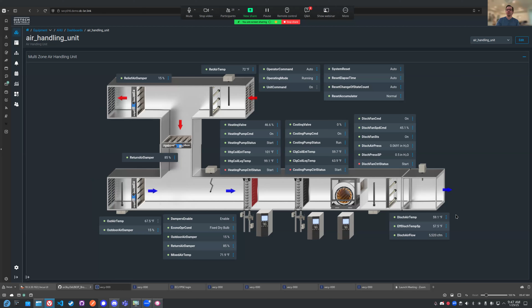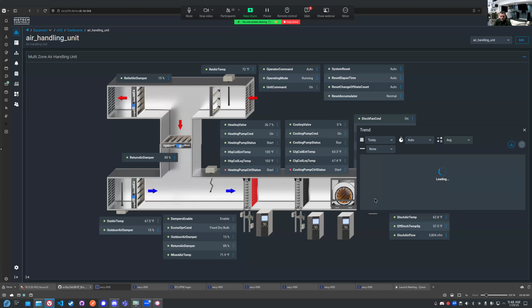One last thing I wanted to show was the discharge air temperature off of the air handler in this test case. You can see it's oscillating between 55 and 70 degrees, so that PID in that controller is not tuned. I wanted to demonstrate this live. This is a graph of the PID loop: the orange line is the set point, the green line is the sensor reading, and the blue is the output. You can see the output is oscillating from about 45% to 74%. So that chilled water valve in operation is just going open, closed, open, closed.